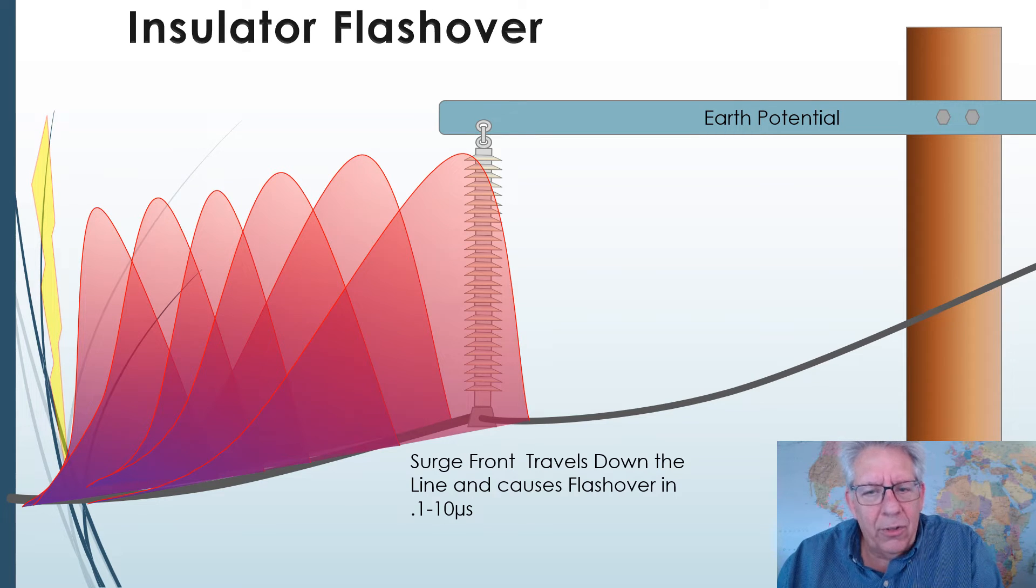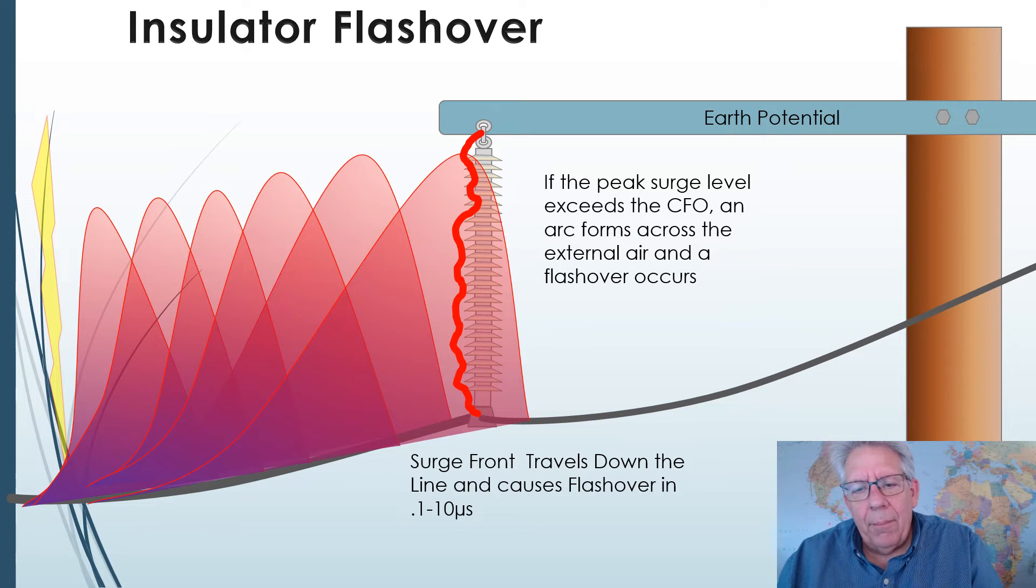So when it reaches the insulator, it immediately flashes over. And this time frame is from 0.1 microseconds to 10 microseconds, depending on how far away the strike was from the insulator.